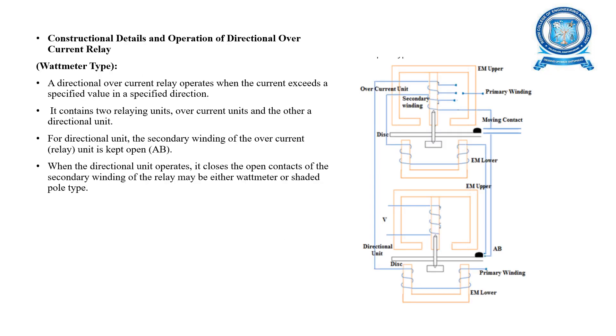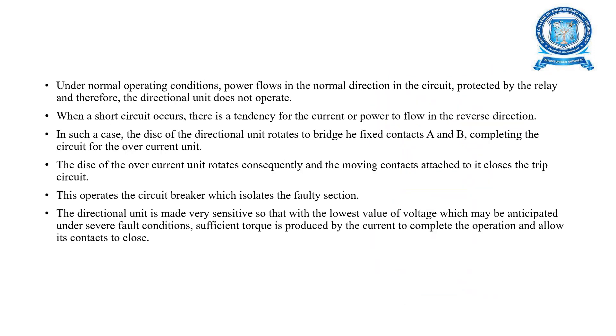Here is the construction and operation of the directional overcurrent relay. The relay operates when current exceeds a specific value in a specific direction. For the directional unit, the secondary winding of the overcurrent relay is kept open at contacts AB. When the directional unit operates, it closes these open contacts. The secondary winding of the relay may be either a wattmeter or shaded pole type. Under normal operating conditions, power flows in the normal direction and the directional unit does not operate. When a fault occurs, the disc of the directional unit rotates to bridge fixed contacts A and B, operating the circuit breaker to isolate the faulty section.